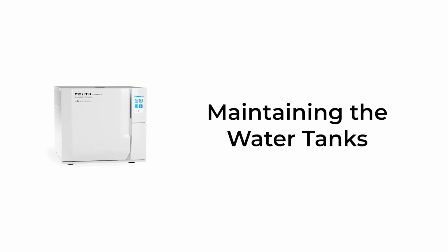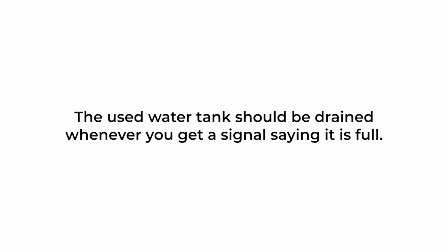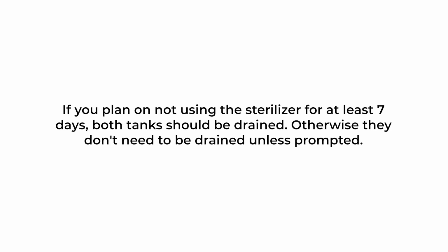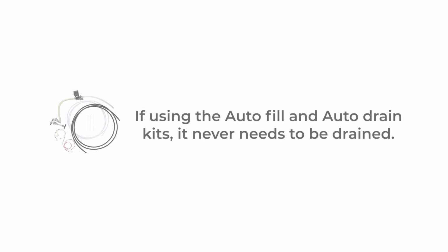Maintaining the water tanks. The used water tank should be drained whenever you get a signal saying it is full. If you plan on not using the sterilizer for at least 7 days, both tanks should be drained. Otherwise, they don't need to be drained unless prompted. If using the autofill and auto-drain kits, it never needs to be drained.